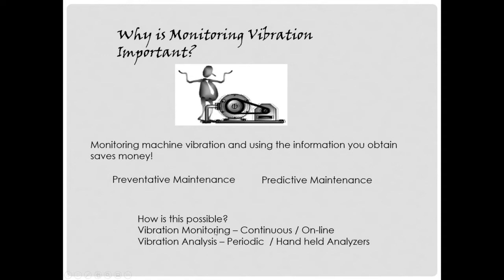We break vibration work into two categories. The first is vibration monitoring, which is a continuous measurement and usually uses an online type analyzer — it's always recording a value of what's going on. The second method is vibration analysis, which is typically a periodic activity, often done with handheld analyzers where we go and check an individual piece of equipment. Some things like exhaust fans won't have online analyzers, whereas gas compressors would. There are different applications depending on the potential severity of unexpected vibrations.